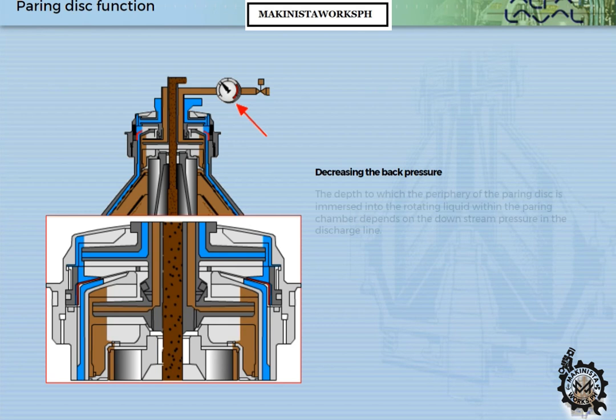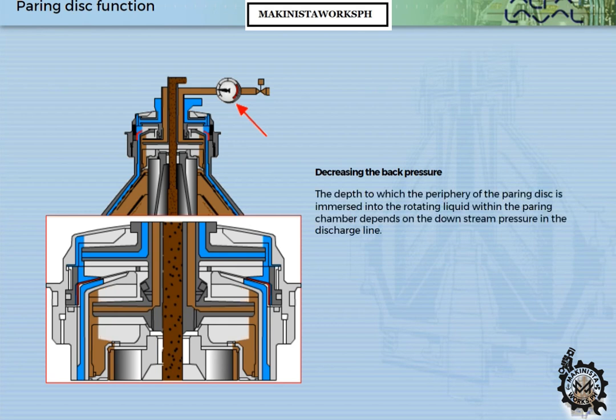The depth to which the periphery of the paring disc is immersed into the rotating liquid within the paring chamber depends on the downstream pressure in the discharge line. As the back pressure decreases, the inner level of the rotating liquid in the paring chamber moves outwards.